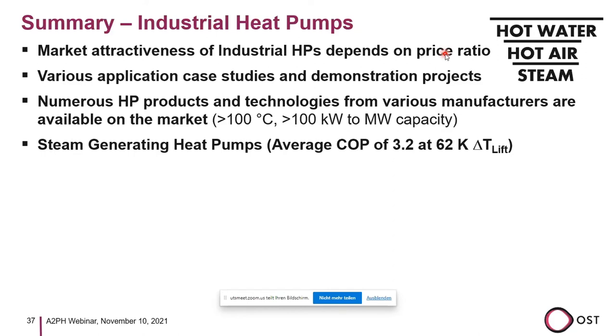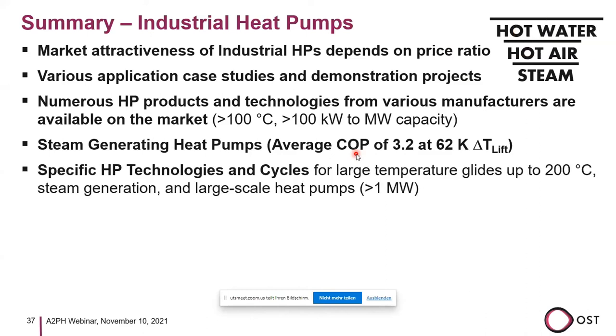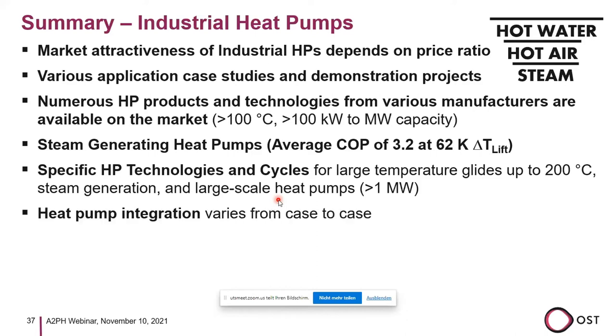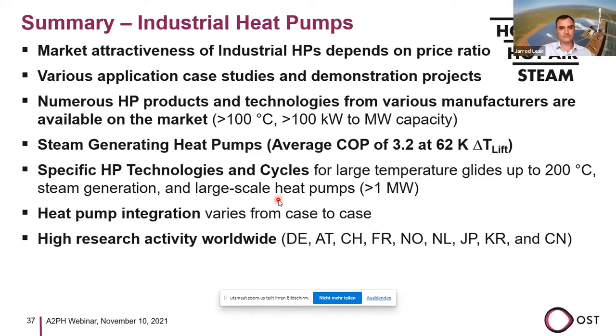Then we have seen steam generating heat pumps, which are already available on the market, but some in the developing phase. We also see some COP values that could be reached. Then there are several technologies for heat pumps and different cycles, especially ones for large temperature glides and cycles for steam generation, which are efficient, and also cycles for large heat pumps. So it's really depending on what heat pump for what application, and what design is the most suitable one. So the integration is varying from case to case. And we see a lot of research activity worldwide.